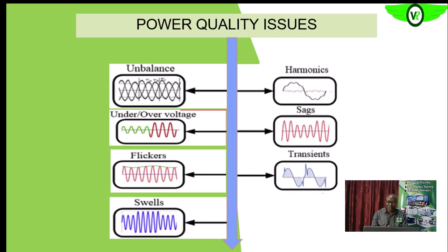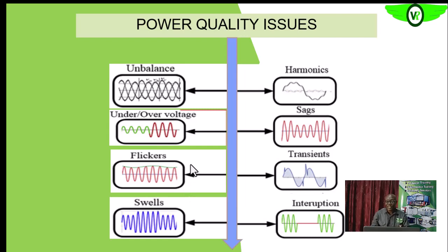Okay, so we have discussed voltage swell before, and this one that we saw here, this is sag. Okay, this is the sag. It lasts for less than a minute, from half a second to about a minute. Then the swell, you see increased voltage that lasts for the same half a second to about a minute as we discussed before. Then we have voltage interruptions.